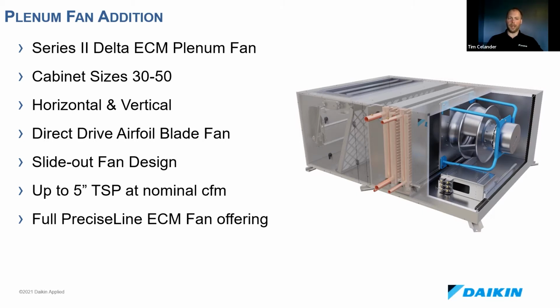This is going to be in the cabinet sizes 30 to 50, which means at 500 feet per minute, you're getting 3,000 to 5,000 CFM. It's going to be available in the horizontal and vertical cabinet sizes. It's a direct drive airfoil bladed fan, so we're using the most efficient fan blades you can. It's fully welded, delivering the CFM it's designed to deliver throughout the life of the fan.